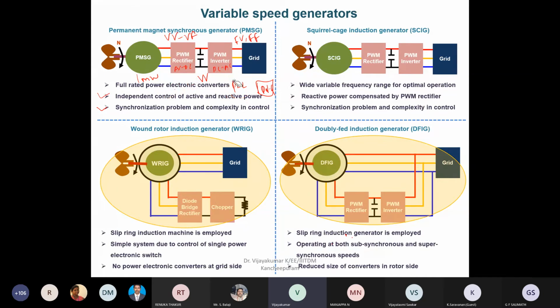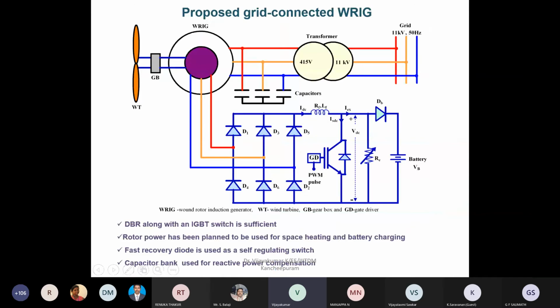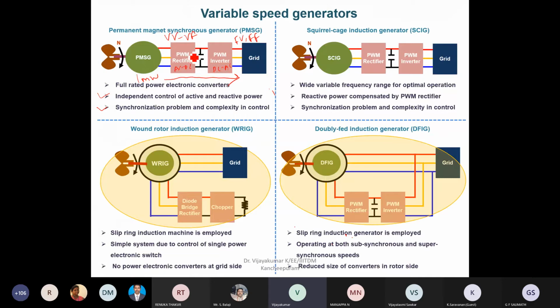When we come to the ratings, if my machine rating is 1 megawatt, all of this 1 megawatt of power is channeled through the converter to the grid. So the rating of the rectifier is also 1 MVA, because I have to channel all the 1 megawatt through it, and the grid side converter rating is also 1 MVA. So the converter ratings are almost equal to the machine rating. That is what we call a full rated power electronic converter.